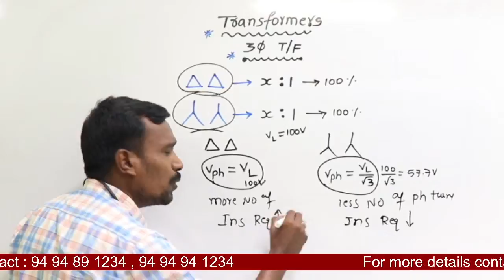As usual, here insulation requirement is also less, while here insulation requirement is more - because of high phase voltage, we need more insulation, and because of less phase voltage, just less insulation is required. So for the same voltage, here more turns and more insulation; here less turns and less insulation.